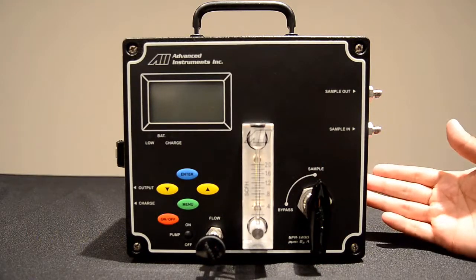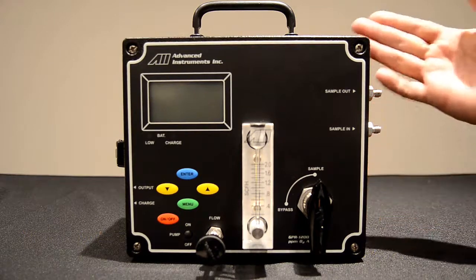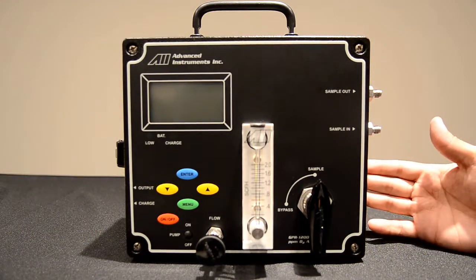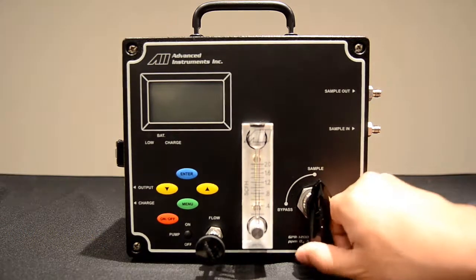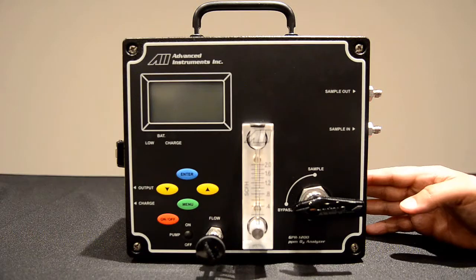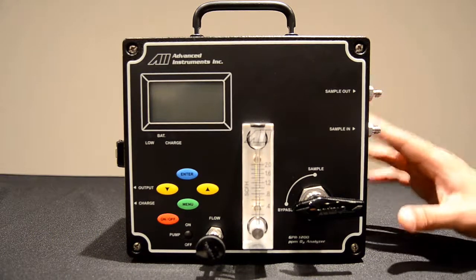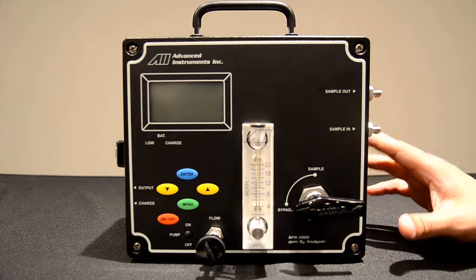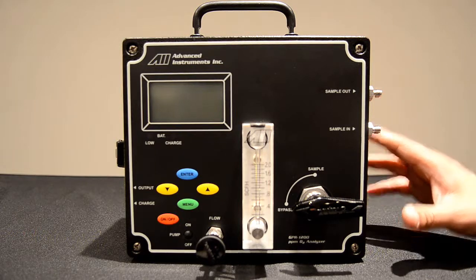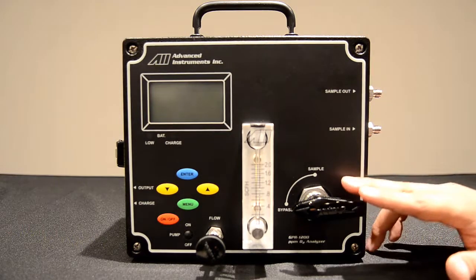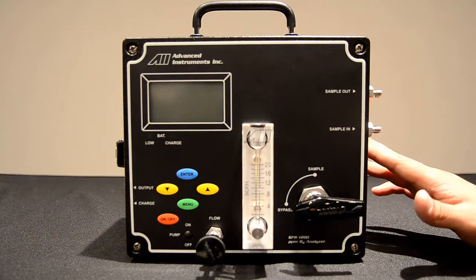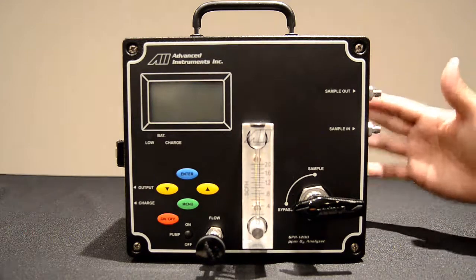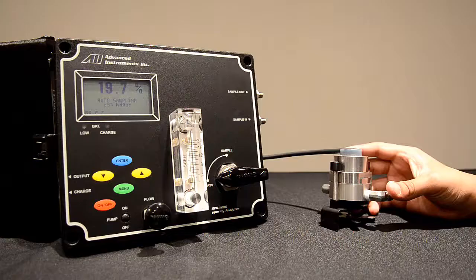The sensor will respond accordingly as the flow goes across the sensor head and your reading will be shown. Once the reading is recorded, you will switch the analyzer back to bypass mode. This again ensures the life of the sensor and will make taking multiple readings easier throughout the day. Again, during transportation and storage the analyzer must be in bypass mode to ensure the safety of the sensor. Those are the basic components of the GPR 1200 oxygen analyzer.